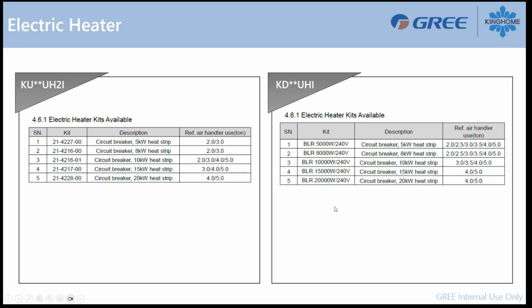So basically, it's really important for you to make sure you match the right heat strip with the right air handler family, and also take a quick look here at the heat strip that we can use versus the tonnage we have. For example, if I have a 10 kilowatt, it's enough for a 3 ton, 3 and a half ton, 4 ton, 5 ton. I cannot install my 10 kilowatt if I have a 2 ton, for example. I cannot do that. It's not inside the manual. So you need to focus on making sure you have the right heat strip, the right configuration before you do your installation.